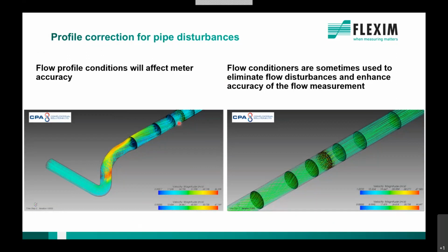What can we do in the field? Well, inline meters, especially custody transfer meters, normally have something like a flow conditioner. They look for the highest accuracy they can get. They have the advantage of having a flow conditioner, whereas the FLEXIM clamp-on meter for the process industry, for process measurements, normally does not have the advantage of having a flow conditioner in the pipe.